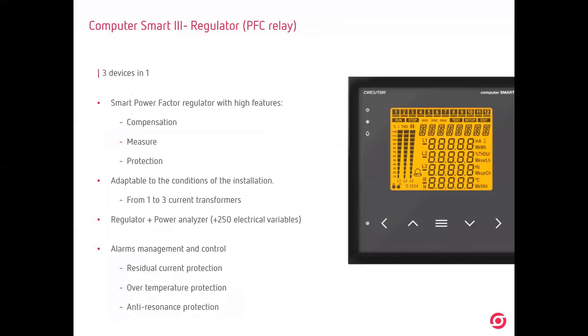This is three devices in one, because we are connecting the steps, the capacitors, in order to decrease the reactive inductive. We are measuring like a power analyzer, okay? And we are protecting. We have the possibility to connect an earth leakage, to have residual current protection, okay? Adaptable to the conditions of installations, we are able to measure with one current transformer or with three. This is very important to take care about, okay? Because if we are paying penalties due to capacitive, or also penalties due to reactive, what we used to do is connect one transformer into the line which has more consumption, okay? But we can be in an overcompensation mode, or we may not compensate all the reactive inductive energy.